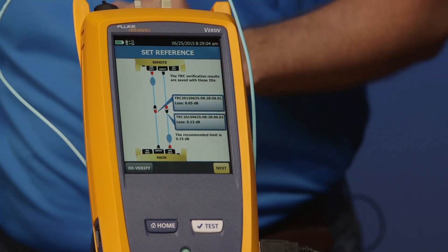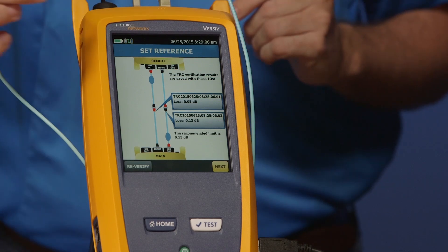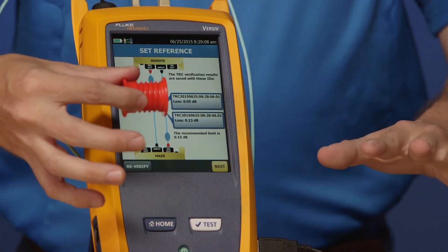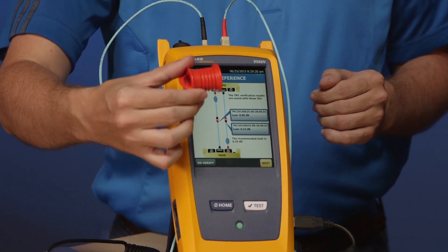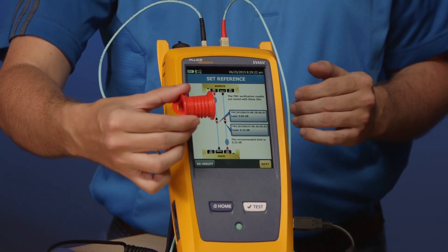Regarding the use of a mandrel: if you don't use these reference-grade test reference cords, I cannot guarantee you're going to achieve better than 0.15 dB for multi-mode or better than 0.25 dB for single mode. Even if you use a mandrel you're still not going to be fully compliant — there's no guarantee. The only way to hit these numbers is by using reference-grade connectors.